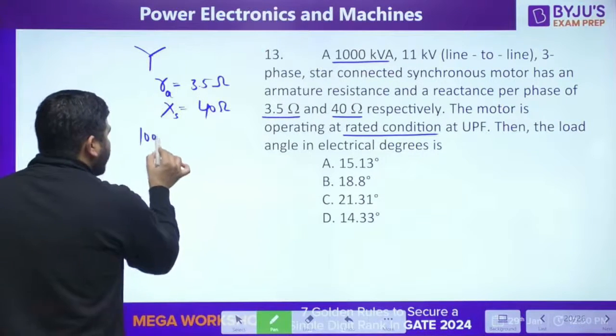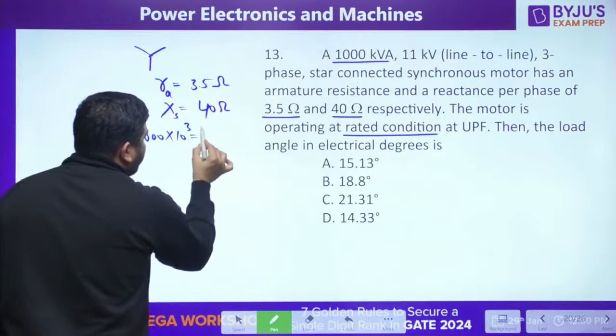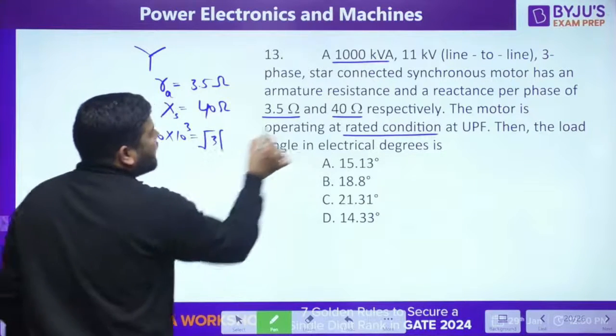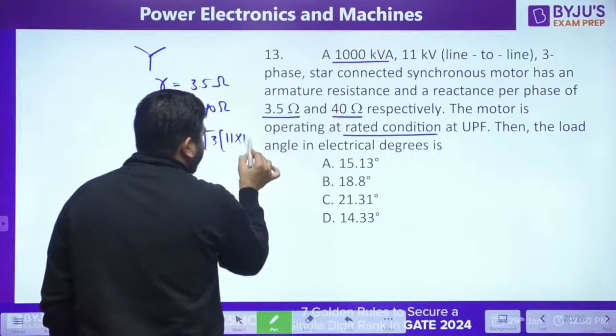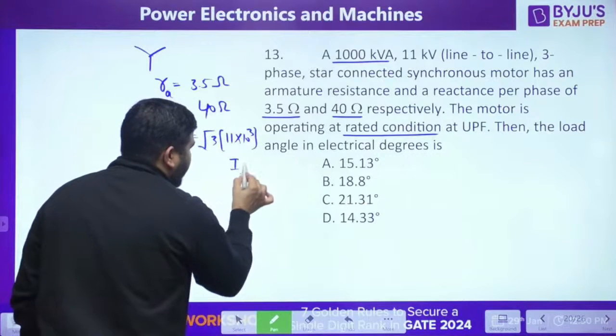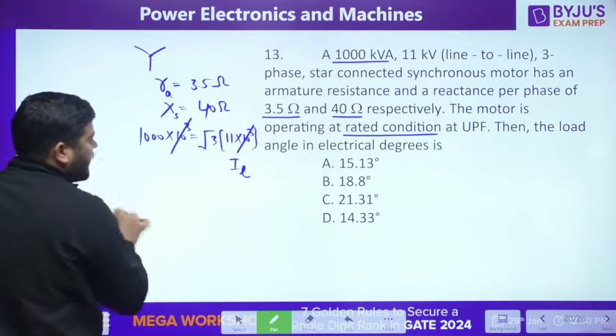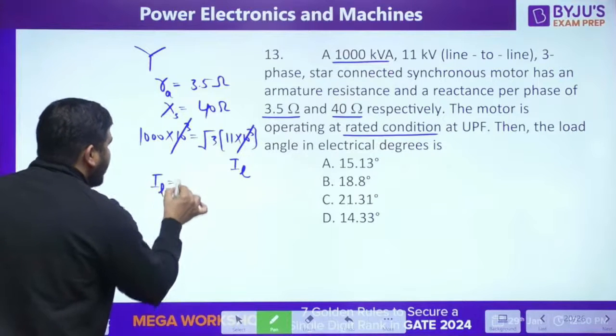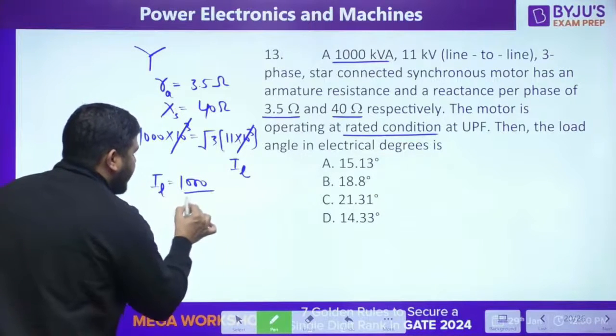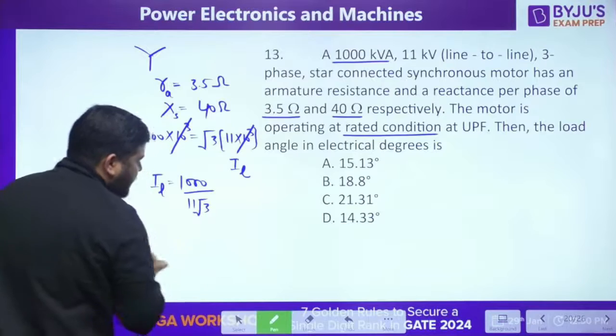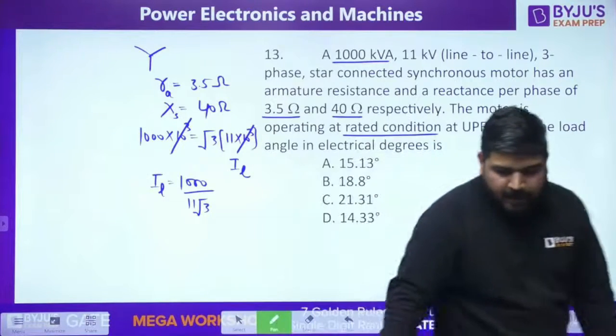1000 into 10 to the power 3 is equal to root 3 VL IL. The rated voltage is 11 into 10 to the power 3, the line voltage, into the line current IL. The 10 to the power 3 cancels, so you can calculate the line current: 1000 divided by 11 root 3. This is my rated line current.